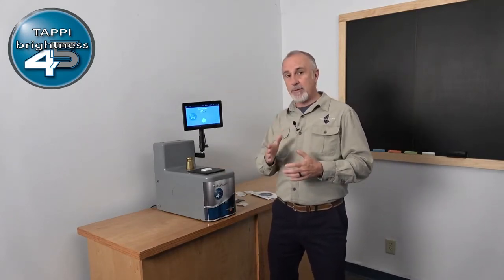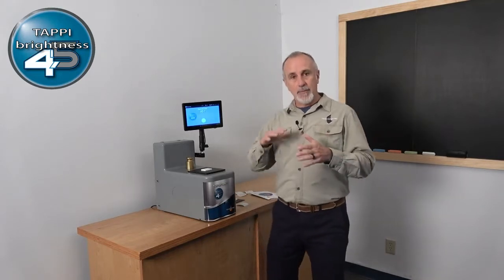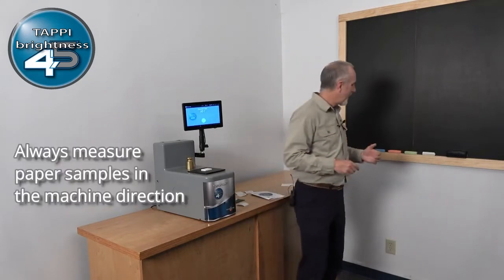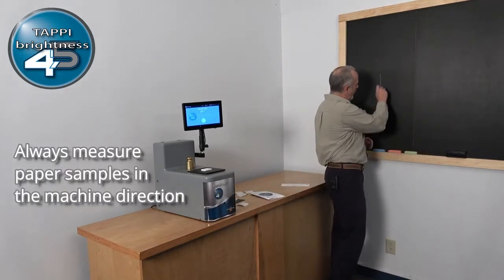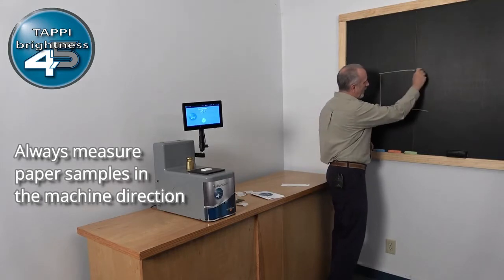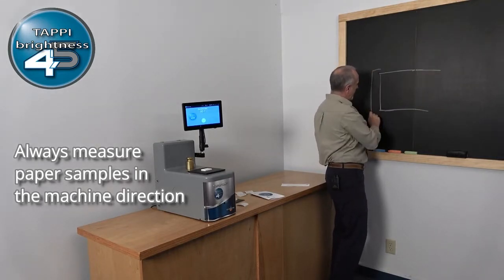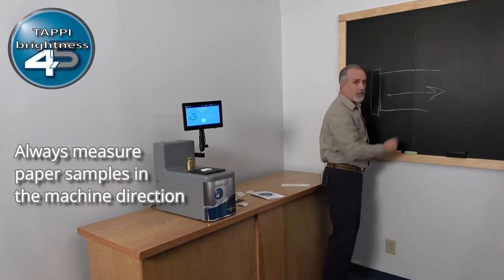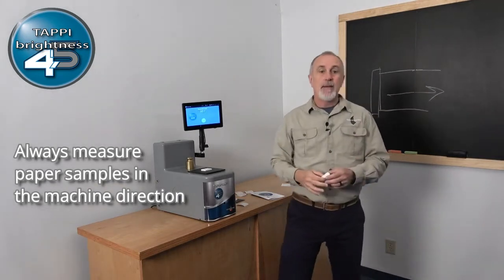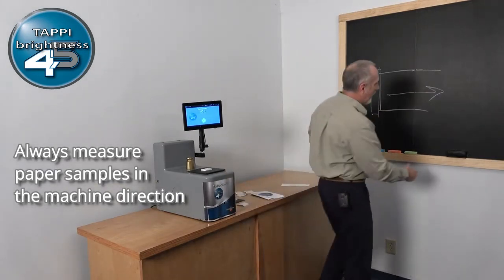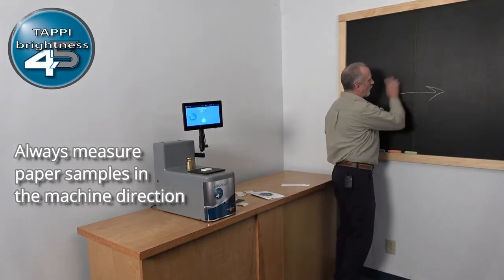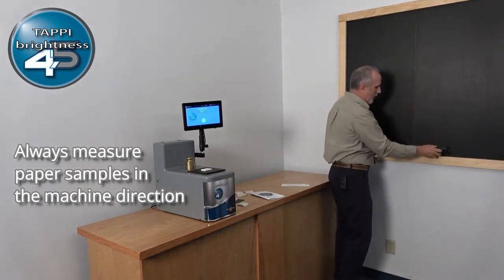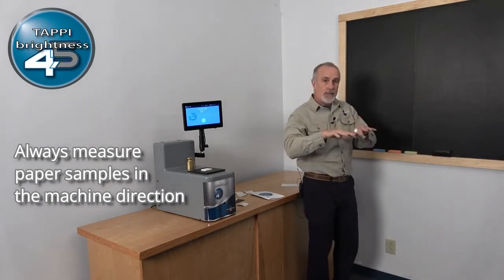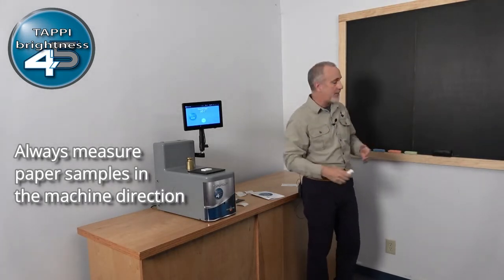Now, in the TAPPI method for the directional instrument, for any directional instrument, you have to be mindful of the machine orientation of the fibers coming off the paper machine. By that I mean if we're looking down on, say, the forming table of the paper machine, and this is the head box here, this is the machine direction of the paper machine. When we're calibrating and making measurements on a directional brightness instrument, we have to be mindful of that because the orientation of the fibers will affect the readings that you get.